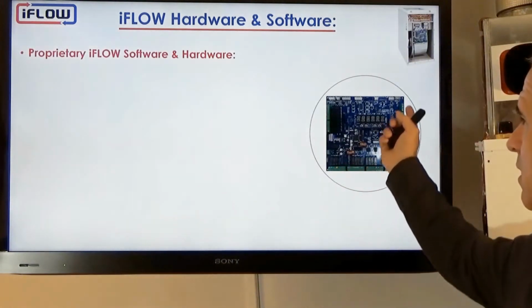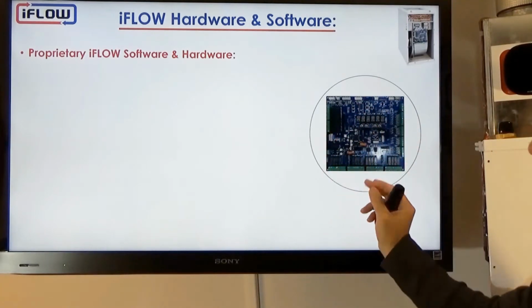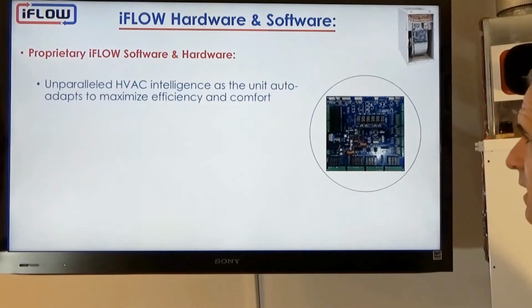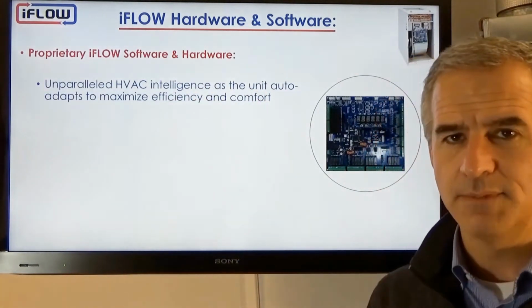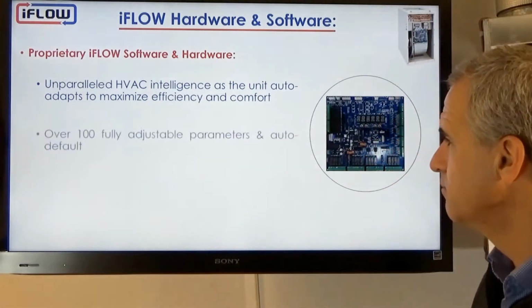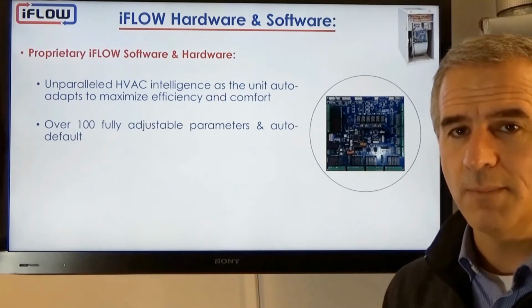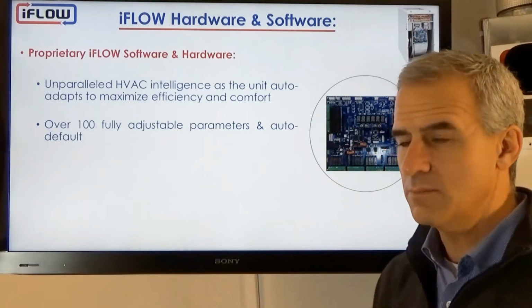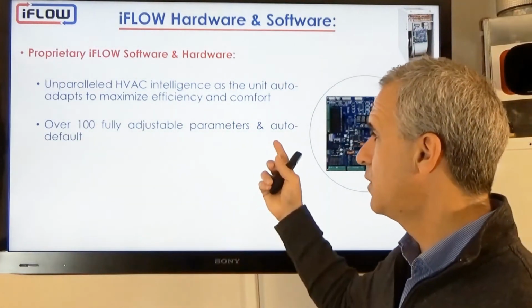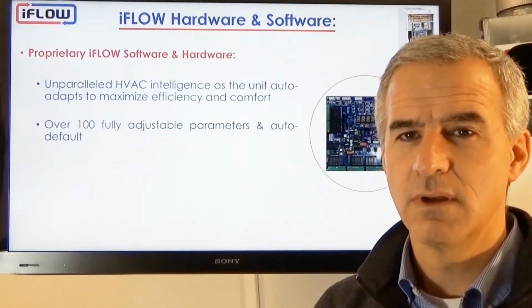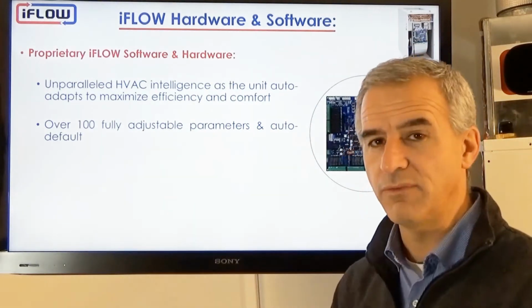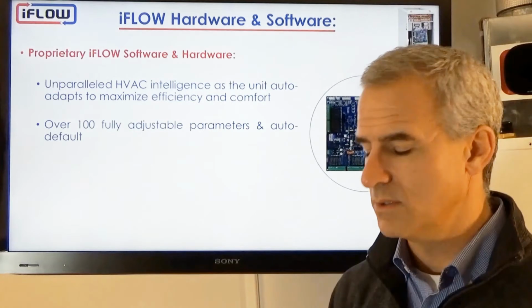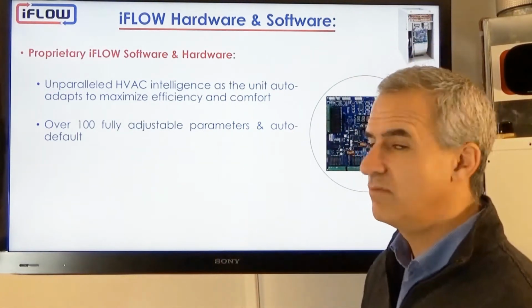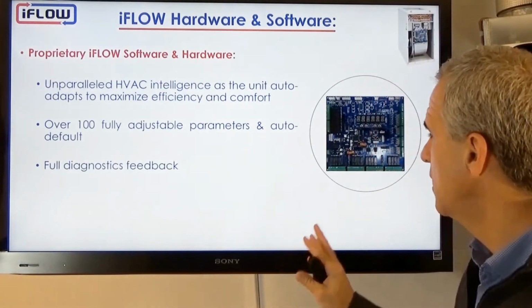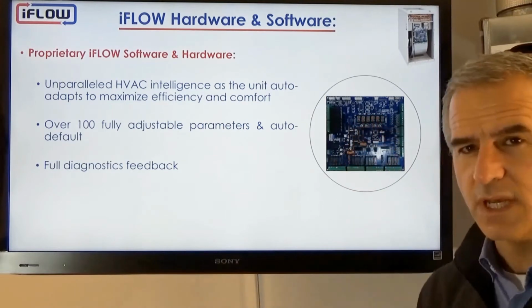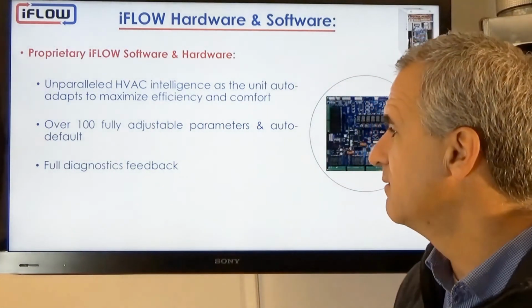Our hardware, this is a picture of our hardware here. This is our 4-zone controller. We have unparalleled intelligence as the unit can auto-adapt to maximize the efficiency and maximize the comfort. There are 100 fully programmable parameters that you can choose from to really fine-tune your system if you would like, or you can use the auto defaults, and for each of those 100 parameters there is an auto default, so you can easily set up if you don't wish to use any of the parameters. They're there if you need them, if you want them, or you can use the auto default just as easily. Get full diagnostics feedback either on the 22 segment LED or on your smartphone app, as we have that capability.